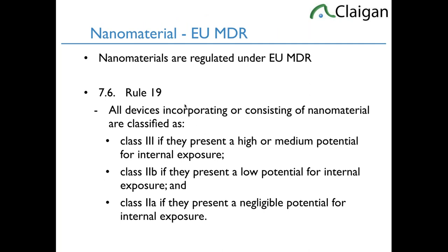The other part of EU MDR — a different section — is about classification. All devices incorporating nanomaterials are classified as Class 3 if they present a high or medium potential for internal exposure, Class 2b if they present a low potential for internal exposure, and Class 2a if they present a negligible potential for internal exposure. Classification is very important and changes a lot of what you do for medical device regulation. You need objective evidence to show how you've addressed nanomaterials in both sections.